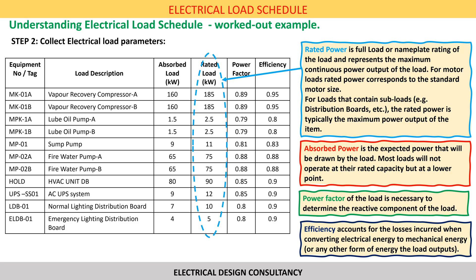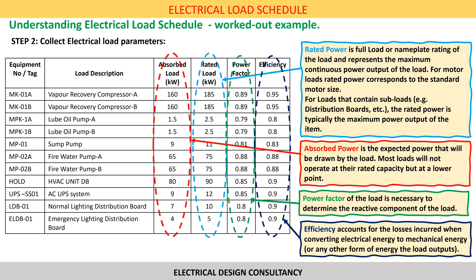Absorbed power is the expected power that will be drawn by the load. Most loads will not operate at rated capacity but at a lower point. For motor loads, absorbed power is based on the mechanical power output to the shaft of the driven equipment at its duty point. The motor is typically sized so that the rated capacity exceeds the expected absorbed load by some conservative design margin. Where information regarding absorbed load is not available, a load factor of between 0.8 to 0.9 is normally applied.